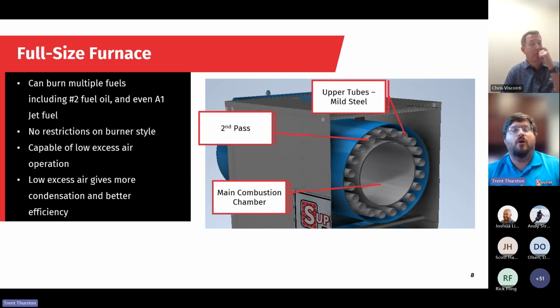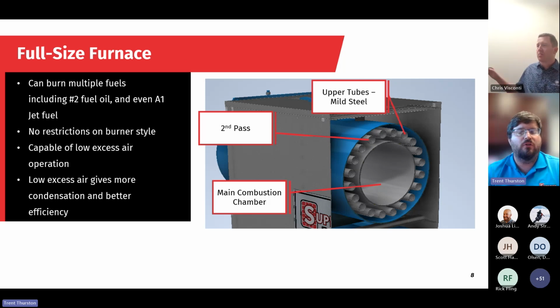One feature we like about our boiler is that we do have a full-size furnace. So this furnace is going to be the same size as any conventional boiler that you see, the 5 square foot per horsepower regular boilers. This allows us to burn basically any type of fuel.